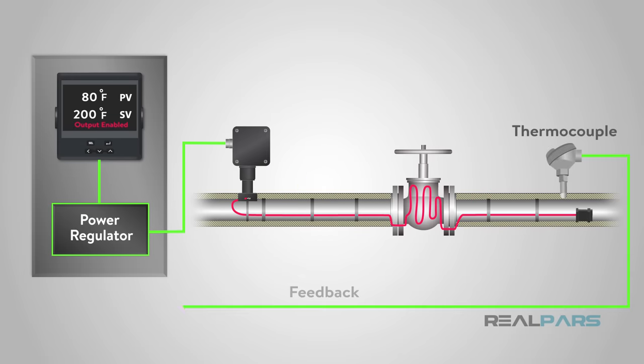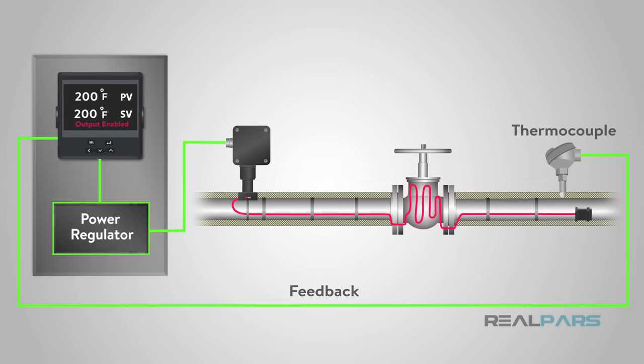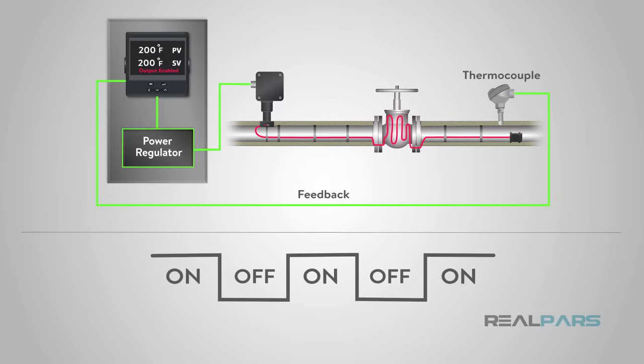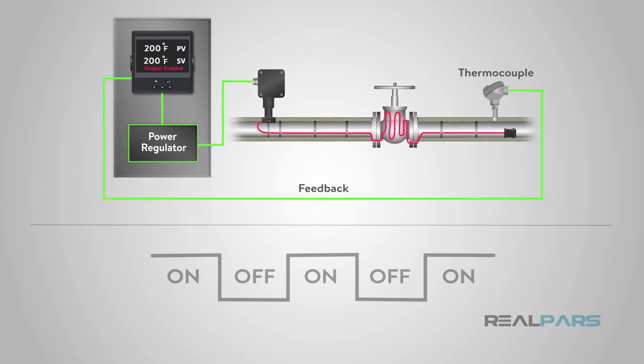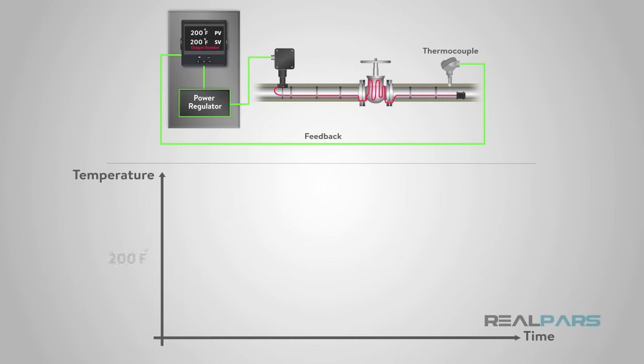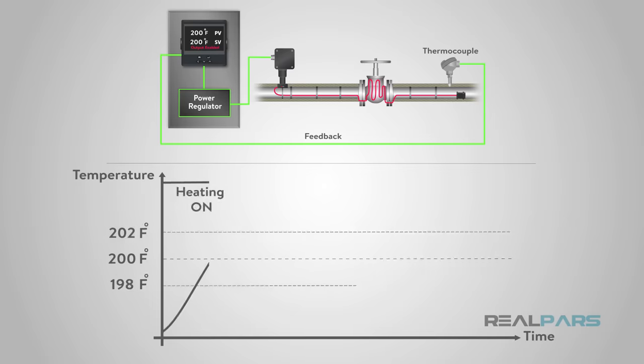The control loop feedback is in the form of a thermocouple to read the temperature. For our example, the PID controller can work as an on-off control for the heat tracing. Along with a set point of 200 degrees, we will set the controller at a couple of degrees above and below 200 as well.